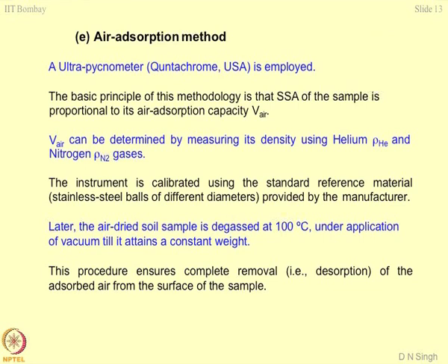The air adsorption method uses an ultra-pycnometer manufactured by Quantachrome. The basic principle is that the specific surface area of the sample is proportional to its air adsorption capacity — the volume of air adsorbed onto the surface. Surface area can be determined by measuring the density using helium gas and nitrogen gas. The contrast between the two densities, multiplied by another parameter, gives you the surface area.